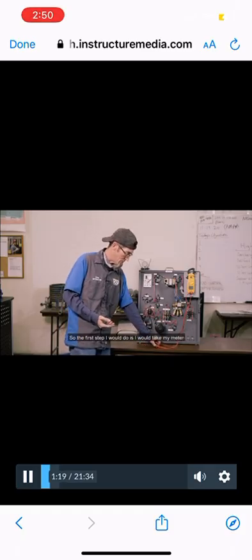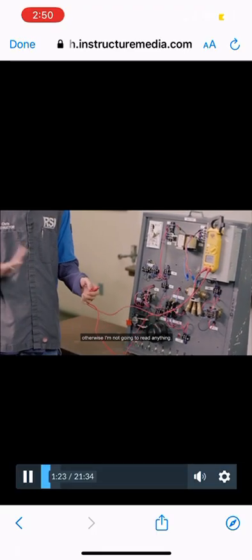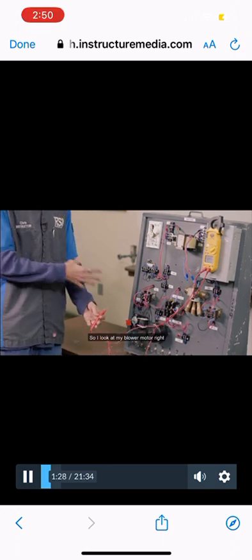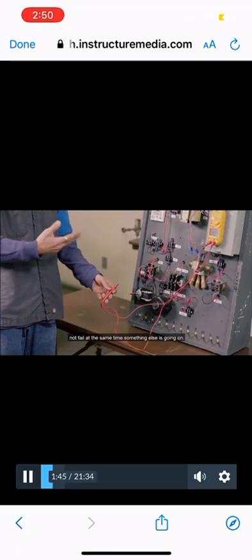So the first step I would do is take my meter leads and, like I said, I should have my meter on, otherwise I'm not going to read anything and it's pointless to try. So I look at my blower motor right here, which is controlled by this relay. These two motors right here are controlled by this relay. This is a contactor, this is an all-purpose relay. Since they're both not on, I can tell in the field that normally these relays will not fail at the same time. Something else is going on.